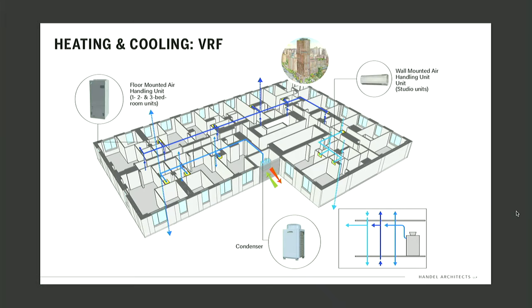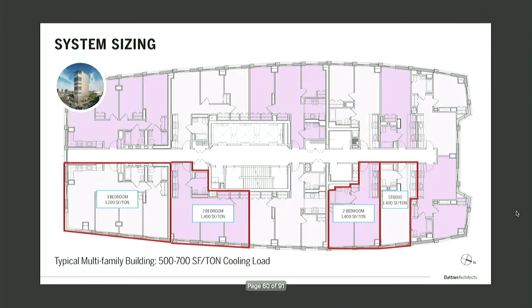And then we're using a different system. On Cornell, we're using perimeter consoles. Here, we're using these VRF closets, where the machine's in here. And then it's a larger machine that sends the heating and cooling ducted throughout the units. So one of the things that we've found with passive house is that the industry has a little bit of catch-up to do. The passive house loads are so much lower than a standard building that the equipment just isn't available out there for the actual loads. So a typical multifamily building has 500 to 700 square feet per ton of cooling load. We're finding it's about half of that for 425 Grand Concourse, and that's probably very similar for my colleagues here.